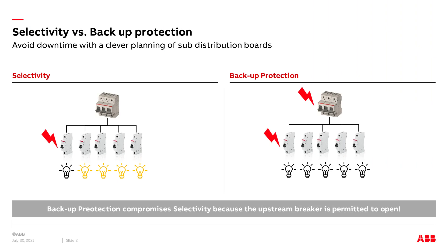Let us first clarify what selectivity and backup protection means. In easy words, selectivity means that in the case of a fault in a downstream circuit, only the closest short circuit protection device, like an MCB, will trip. The rest of the installation stays live. In electrical systems of a building, coordination is normally done to reach a high level of selectivity.